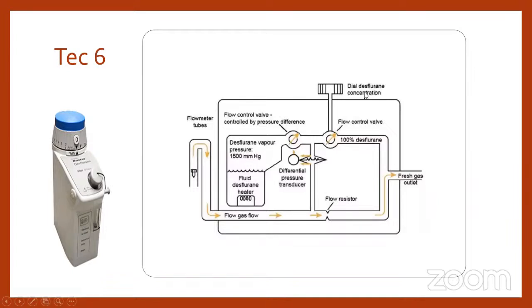And this is the dial of concentration. We can reduce or increase the desflurane. It basically has 100% desflurane coming out of this, and it mixes with the fresh gas and goes up. If the pressure of fresh gas is more, it gives a signal to the CPU that is present inside the desflurane vaporizer. So a differential pressure transducer will be there inside the circuit. It automatically reduces the amount of desflurane that passes through. So it is a safety mechanism.